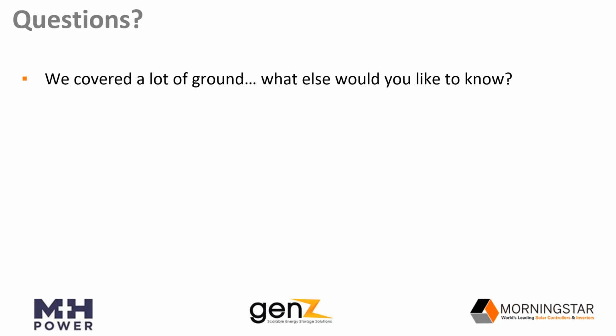Let's see. The questions we had. Here's a question for Albert. Is there any way you can read the actual state of charge of the genZ battery, or do you just estimate this from voltage readings? Yep, I can answer that. With Morningstar, we are relying on the voltage reading, but with other systems, we've actually relied on shunts, and we just count on the coulombs in and out, and that would give you an estimated state of charge of the battery. Very good. All right, terrific.